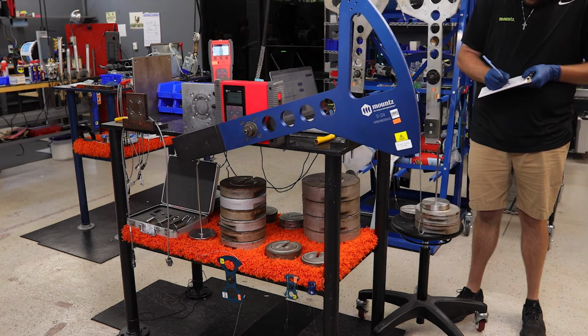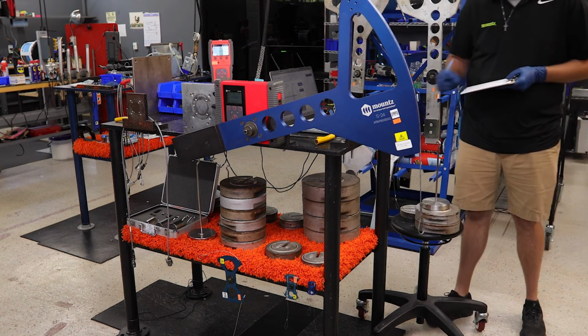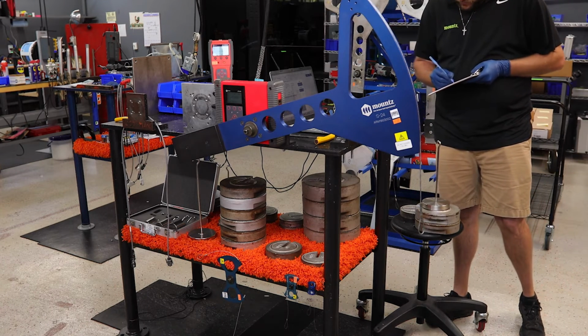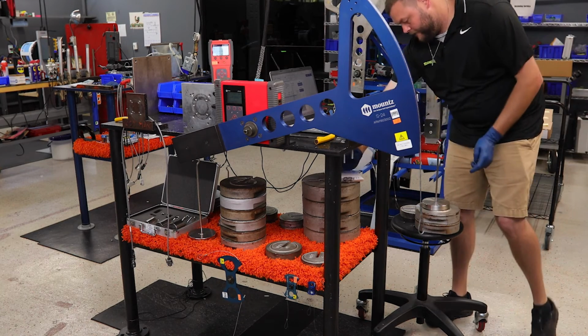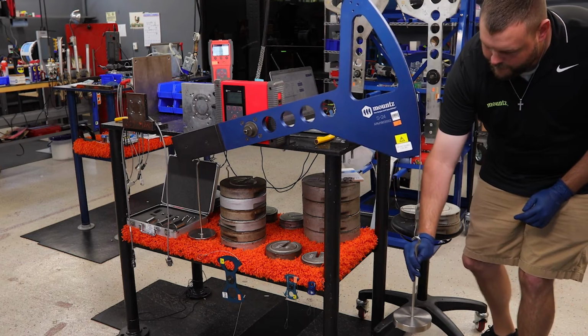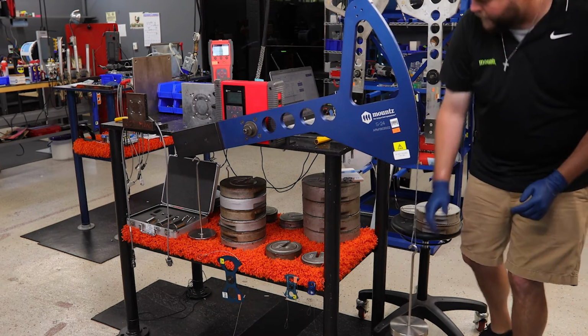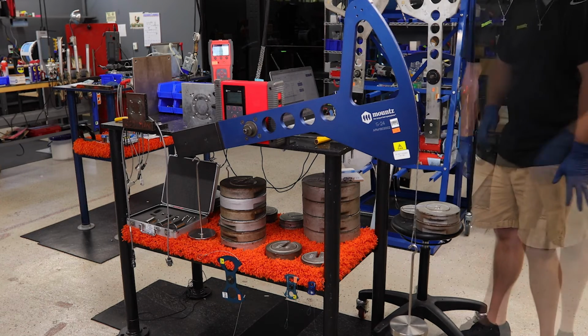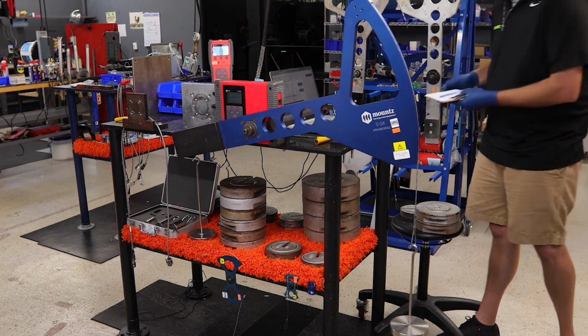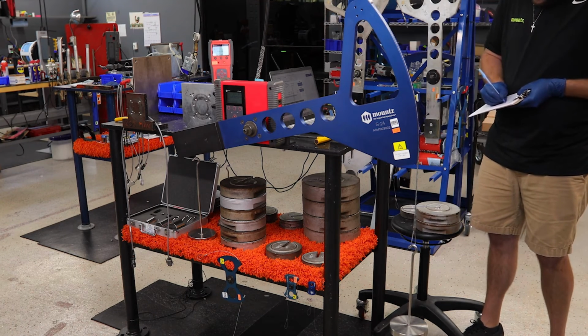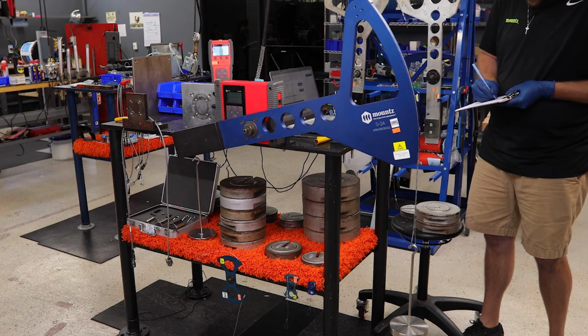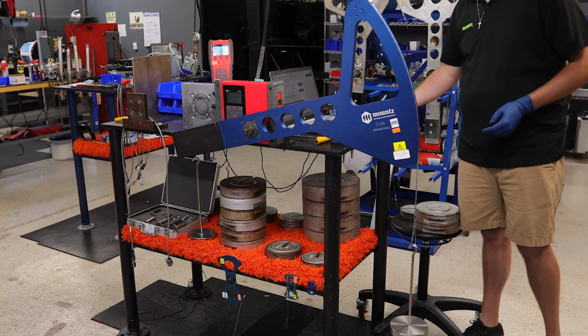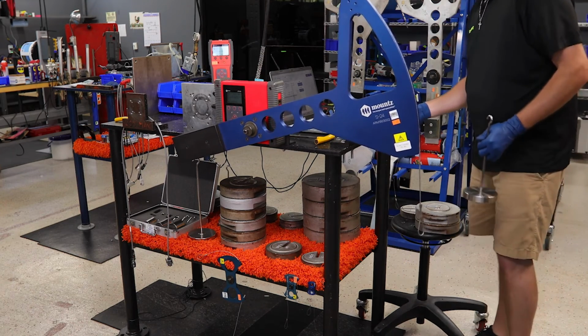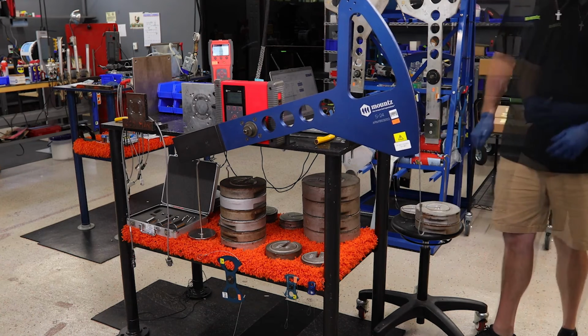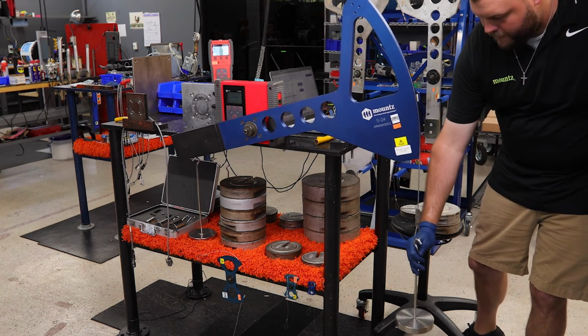So once the exercise has been done, we will then begin the three-point calibration with the use of the software that is connected to the analyzer. So it is measuring the resistance and it is calculating what the amount of weight is, and it's doing its calculations, and it is putting the calibration data. Once the entire process is finished, it loads that information onto our ARC2 chip that's within the sensor itself. So this will allow you to basically plug and play with either a PTT or our LTT if we are adding an additional sensor.